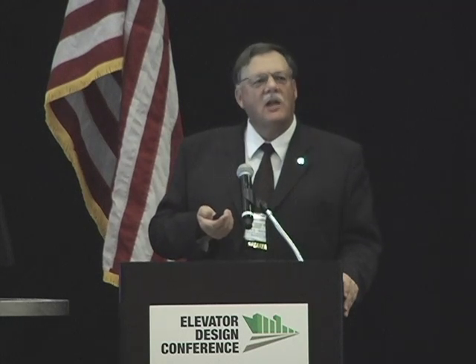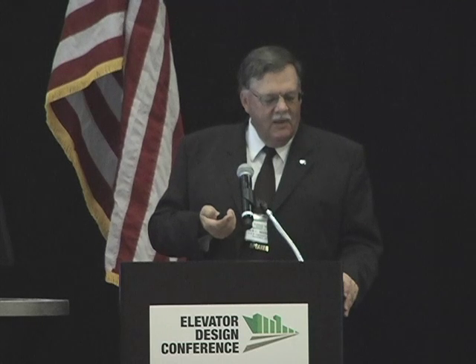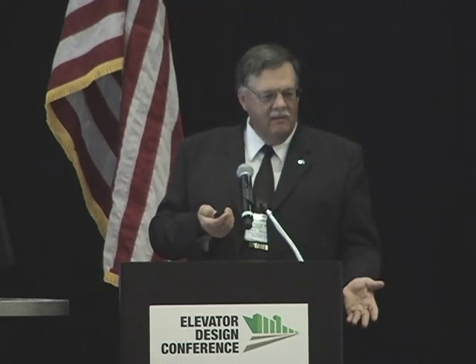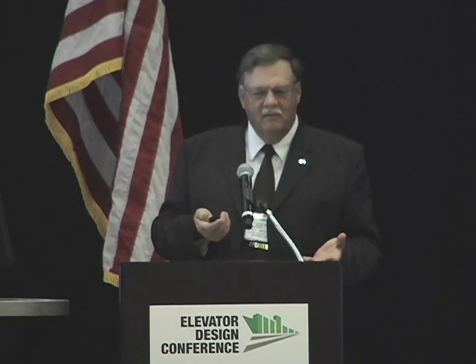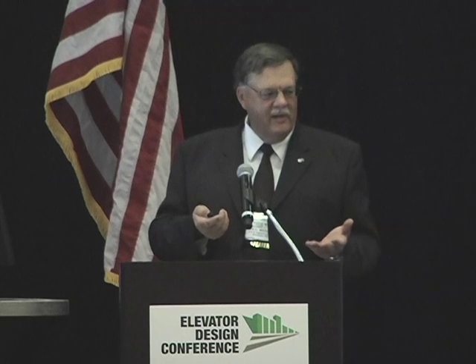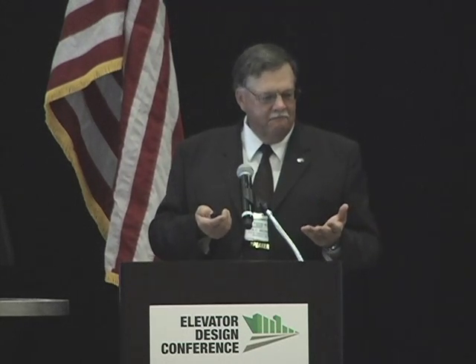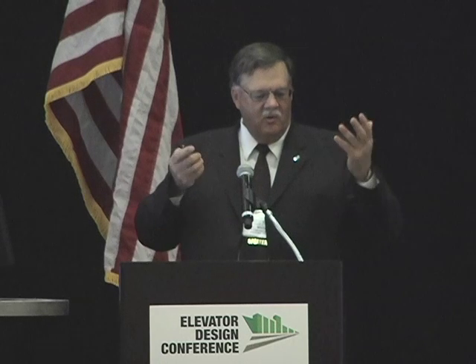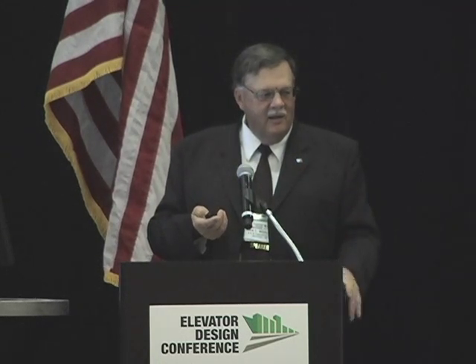One of the biggest issues you have with your whole arc flash access safety is if you want to do an infrared scan. You can't do an infrared scan if it's off. The only way you can do an infrared scan is when the current's flowing through the circuits. So it's kind of a catch-22: I have to open the door to do my infrared scan, but the label on it says I have to wear this whole suit to open the door. And so it gets to be a real issue in some of those cases.